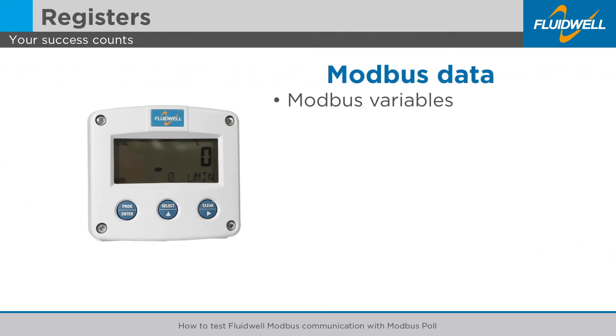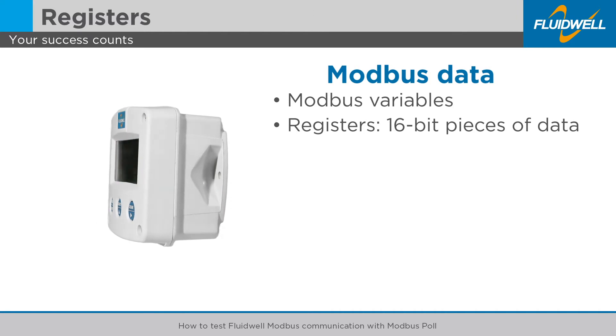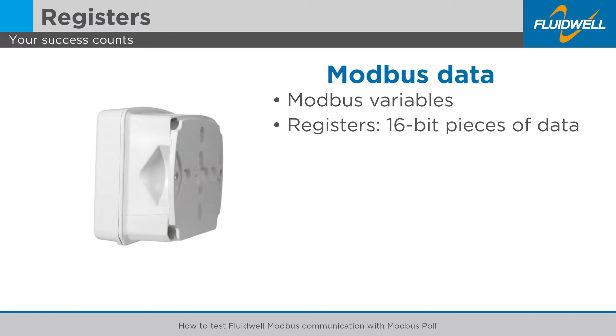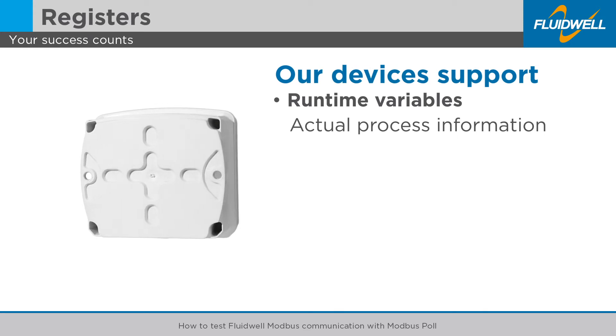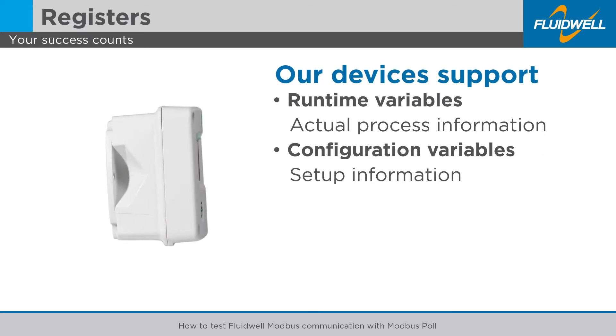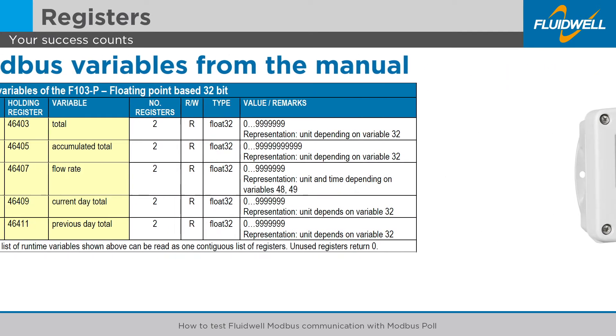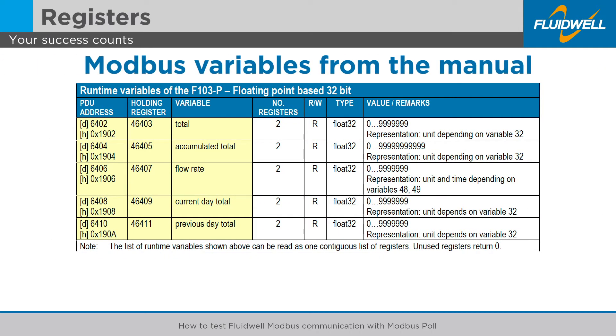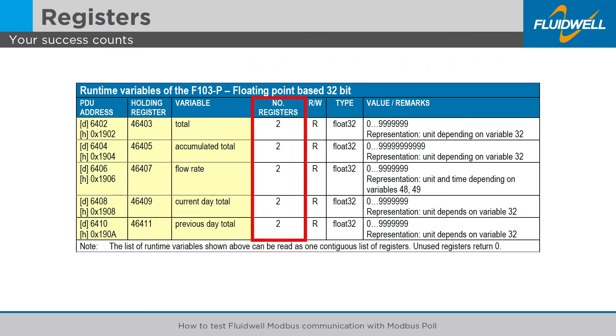Modbus data or variables are most often read and written as registers, which are 16-bit pieces of data. Our devices support runtime variables with actual process information, and configuration variables with setup information. The variables are indicated in each manual with PDU address in both decimal and hexadecimal codes, holding register number and number of registers.